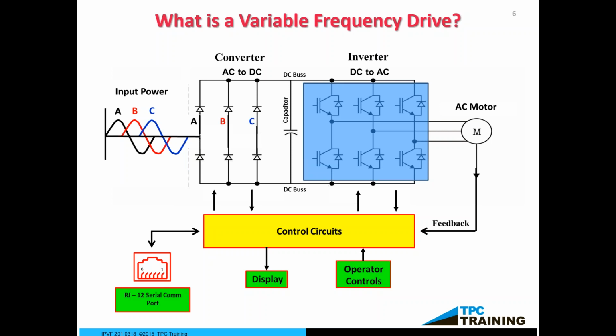So when we're troubleshooting, and that's one of the things with these drives, we must know what you're supposed to get before you look at it on the display. So the long and short of these drives: AC to DC, DC to AC, the output is a pulse width modulated signal. Now, they're kind of misleading you when they say variable frequency drives. It's also a variable voltage and frequency drive. So if I had 480 volts and 60 hertz, just as the big picture here, and I know we've gone over a lot in the last 15 minutes or so, it's not just a variable frequency drive, it's also a variable voltage and frequency drive.